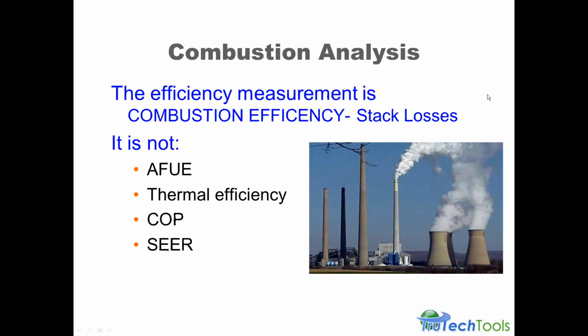So what isn't combustion efficiency or combustion numbers? Basically, it's a measure of stack loss, but it is not a measure of AFUE, or annualized fuel utilization efficiency. It's not a measure of thermal efficiency, say from an ASHRAE standard, or the coefficient of performance, or a SEER, a seasonal energy efficiency ratio. It's none of the above. Combustion efficiency is basically a measure of steady state stack loss to tell you what the steady state operating efficiency is. So even though higher AFUE appliances will come from higher combustion equipment that's operating at higher combustion efficiency, they are not one and the same.